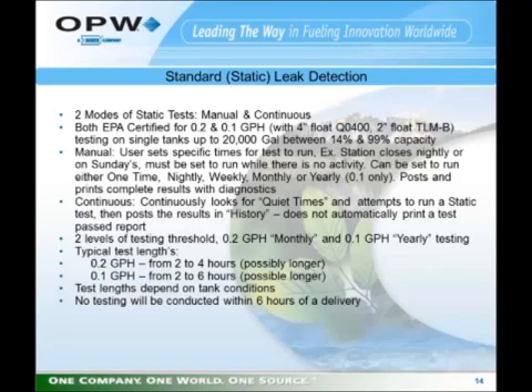Therefore, you can program a manual test to begin at a specific time. However, you cannot program a test length nor an end time for the test. And no test will be performed within 6 hours of a delivery into the tank.